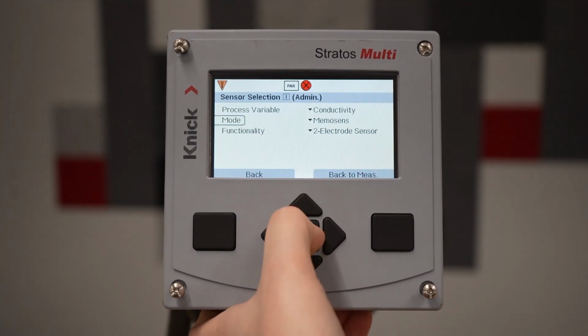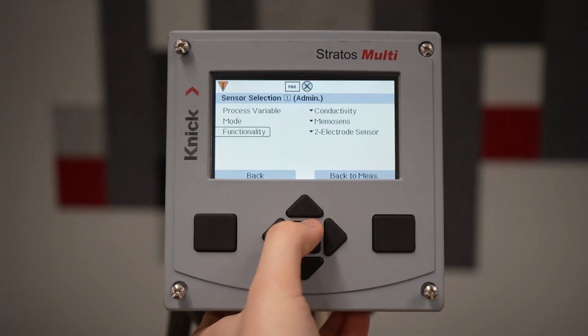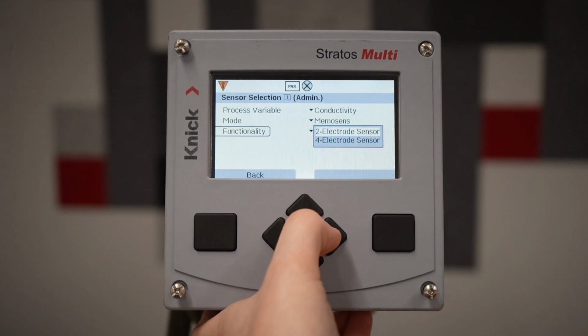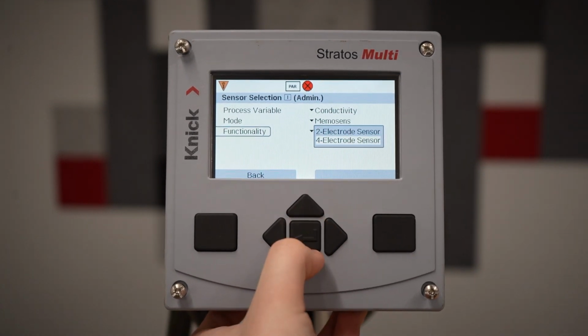Once you select that, make sure Memosens is selected for mode, and then in functionality, ensure that you have a 2 electrode sensor selected if you're using a 2 electrode, and a 4 if you're using a 4.